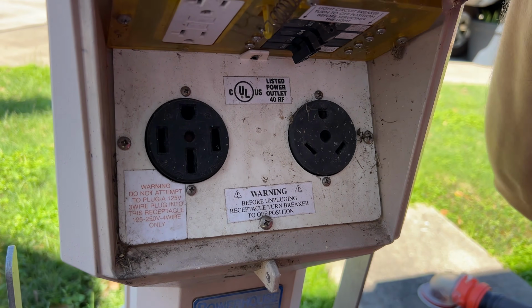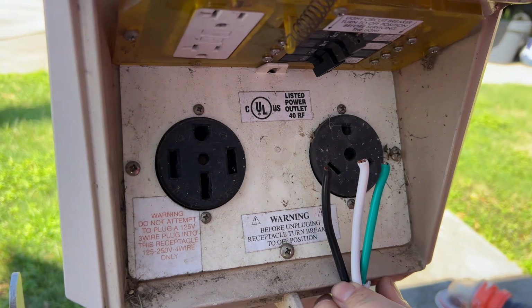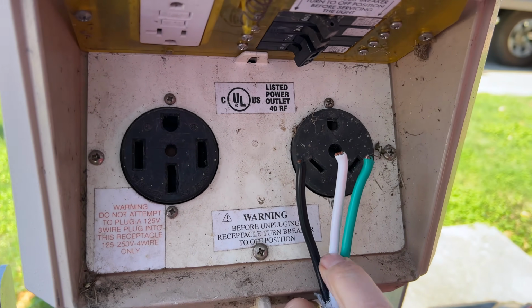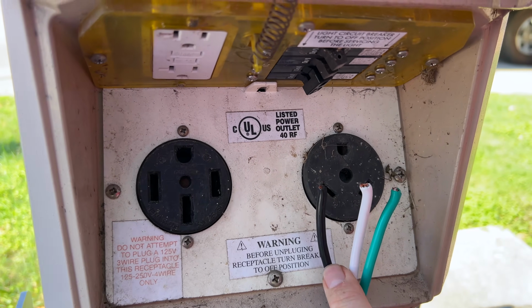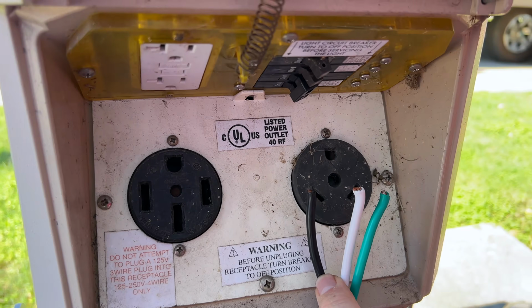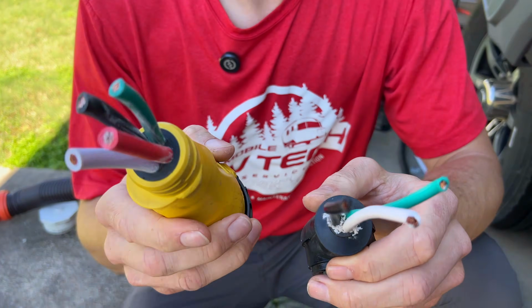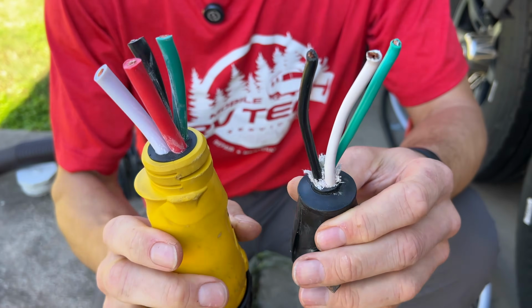Now in the 30 amp RV, we have 3 wires inside of that - 1 hot leg, 1 neutral, and 1 ground. In a 30 amp wire, 120 volts gives you 3,600 watts. The difference between these, as you can see, is the 50 amp has much thicker wires and is more heavy duty.